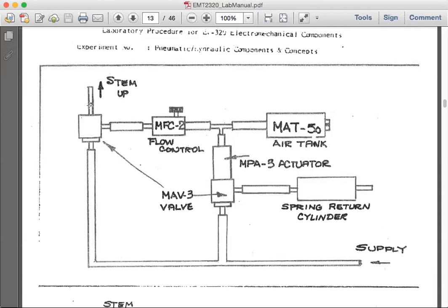It vents through the hole in the stem. Also here, it vents through the hole in the stem. And since the actuator is deactivated, at the bottom of the actuator, there is a hole that allows the pressure that vents through the stem, vents farther outside, out of the system. So your stage number 4, this is blue, everything is blue, and the piston returns.